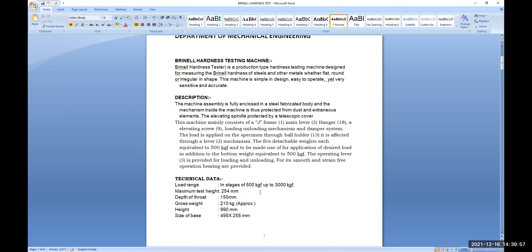So what are the different loads? For Brinell indenters, we don't have any diamond or any other hard materials, but we have only hardened steel balls for loading. This hardened steel ball will be fixed to the plunger, and the pressure is applied by means of a special holder, which houses the indenter, which is a round ball inside the hole, and this holder also has a thread. It can be fixed to the topmost spindle of the machine.